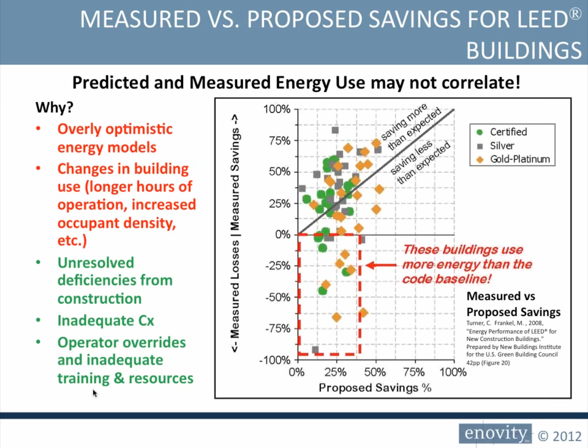When commissioning is inadequate and there are unresolved deficiencies, operators given the building to operate often just throw things into what I like to call manumatic, to deal with customer temperature problems, putting band-aids on a building that's not operating optimally to begin with. That's enough on this slide. Let's go to the next slide, please.